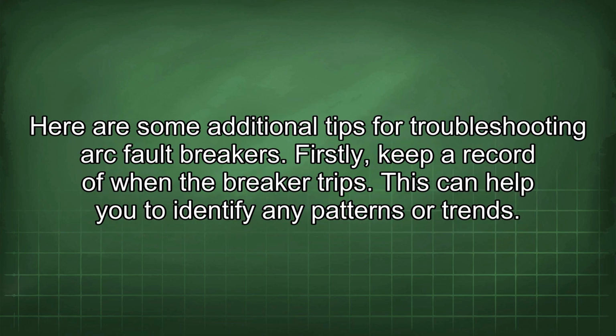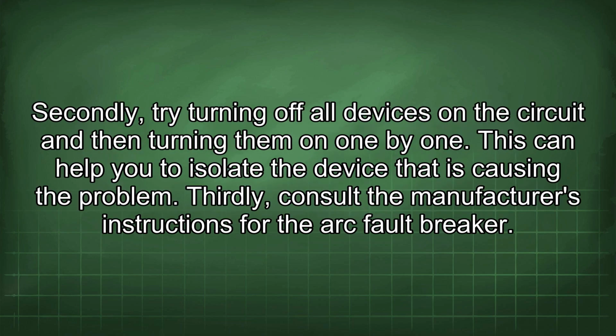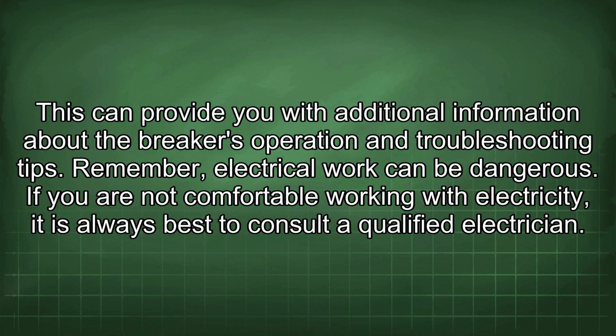Here are some additional tips for troubleshooting arc fault breakers. Firstly, keep a record of when the breaker trips. This can help you to identify any patterns or trends. Secondly, try turning off all devices on the circuit and then turning them on one by one. This can help you to isolate the device that is causing the problem. Thirdly, consult the manufacturer's instructions for the arc fault breaker. This can provide you with additional information about the breaker's operation and troubleshooting tips.